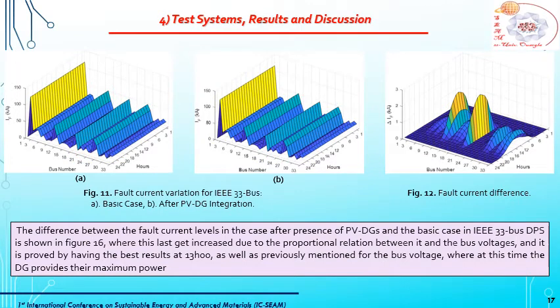In Figure 11 is mentioned the fault current variation for the second test system for both cases before and after integration of PVDG, and the difference between them is mentioned in Figure 12, where the same remark is that the fault current is increased due to the proportional relation between it and the bus voltage, and it is proved by having the best results, the same as the case of bus voltage, at midday as previously mentioned.